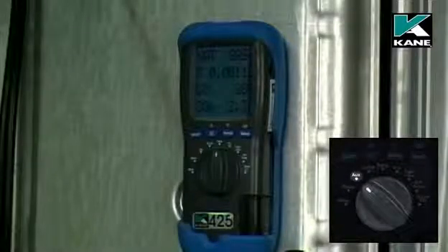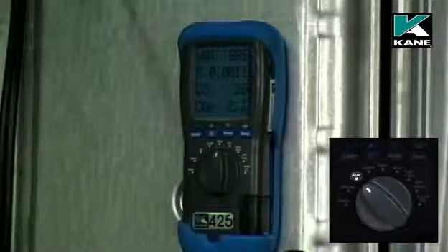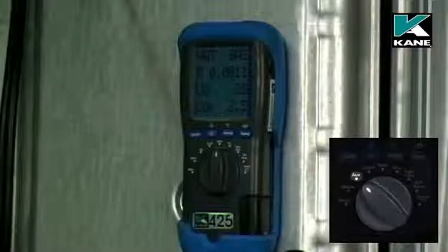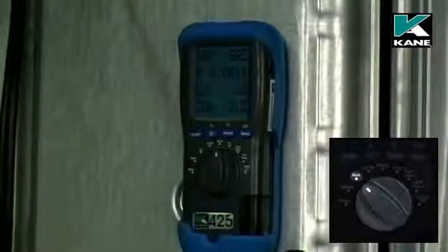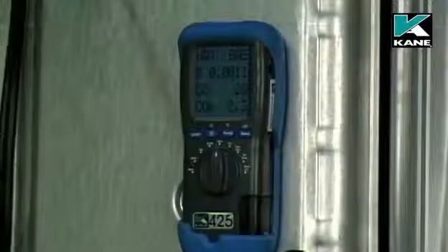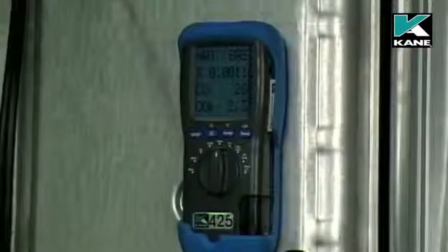Combustion readings can also be logged by pressing the send button for 2 seconds. The log number is briefly displayed on the top line. These readings have been stored as log number 8. The memory can store up to 99 combustion readings. Logged readings can be viewed and printed via the menu.